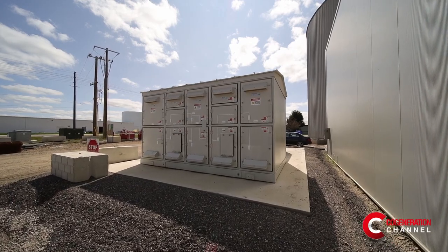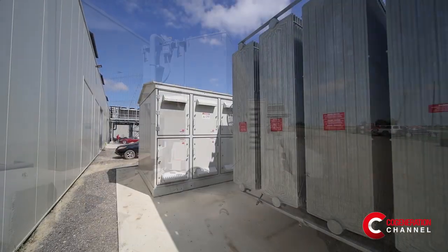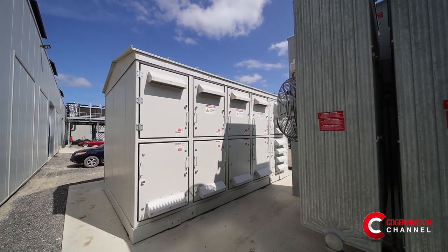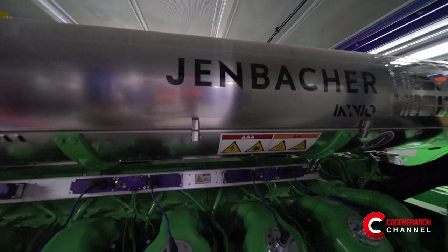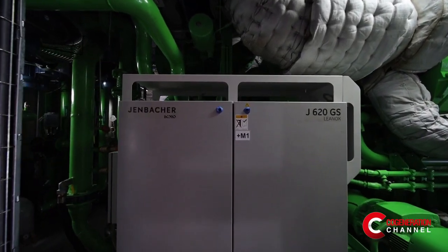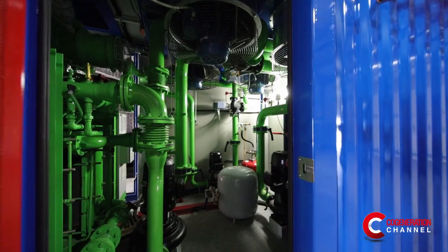Currently, we take natural gas that is used to produce electricity into the grid, and the byproduct is heat which we use in our greenhouse. The COGEN system itself is very sophisticated in that it ties directly into our greenhouse climate controls. So when the COGEN is operating and producing heat, the greenhouse is aware of the amount of heat created and puts it into the greenhouse instead of using our own boilers to produce heat, making sure that we're fully efficient.